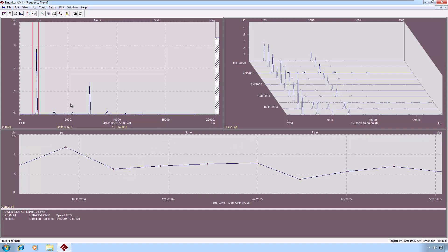And you can grab that band and move it anywhere in the plot. So for example, if I had some developing haystacking on my spectraplots, and I wanted to see how long that energy was present in the trend, and whether this was a recently developing phenomena or something that's been going on for a while.